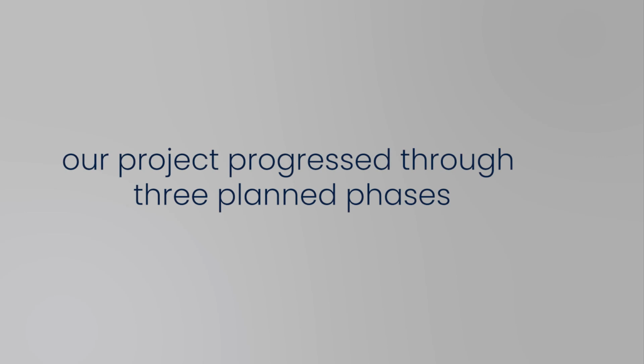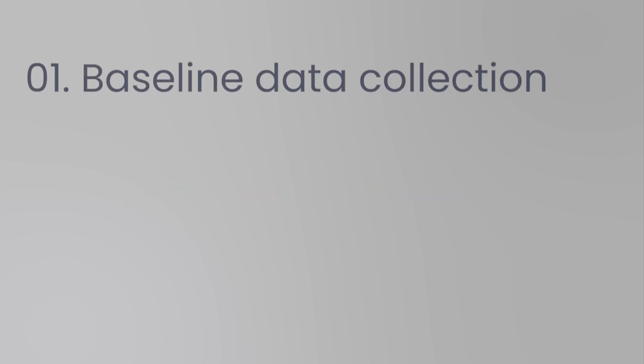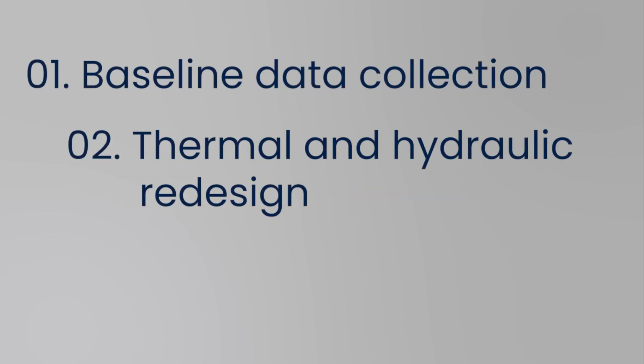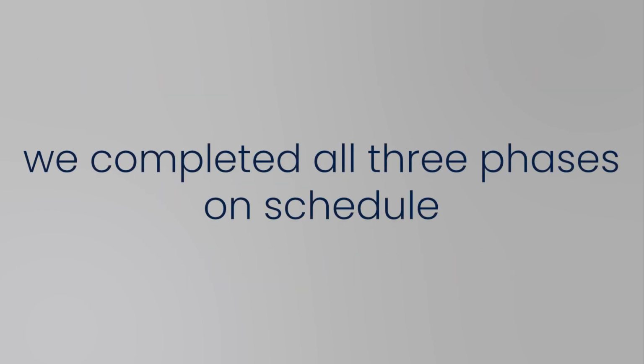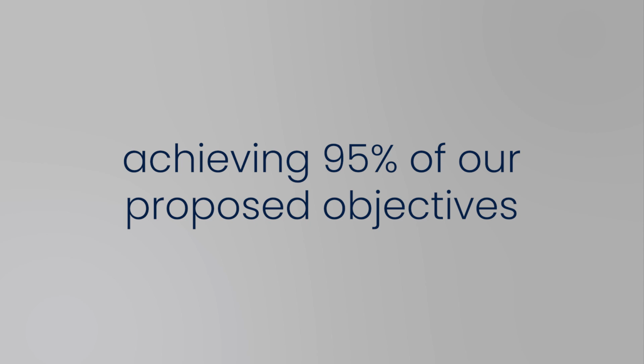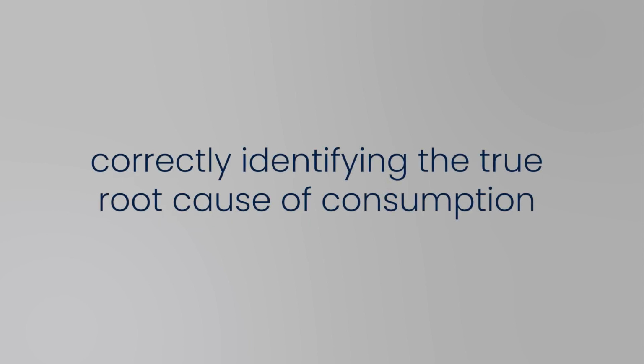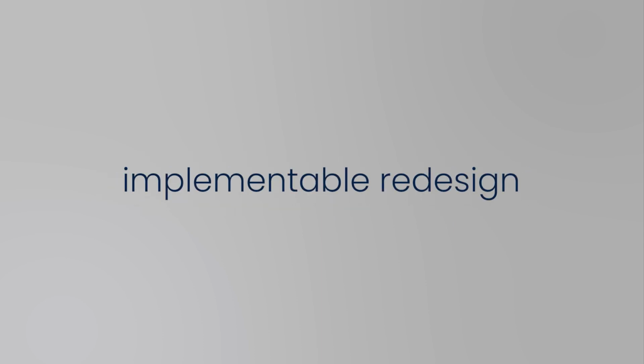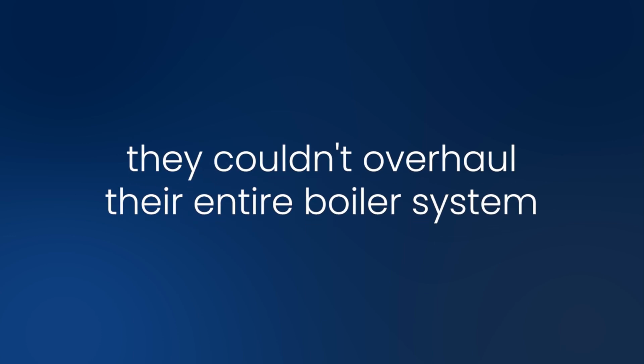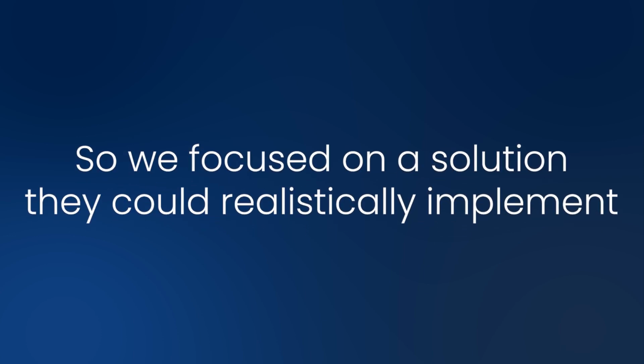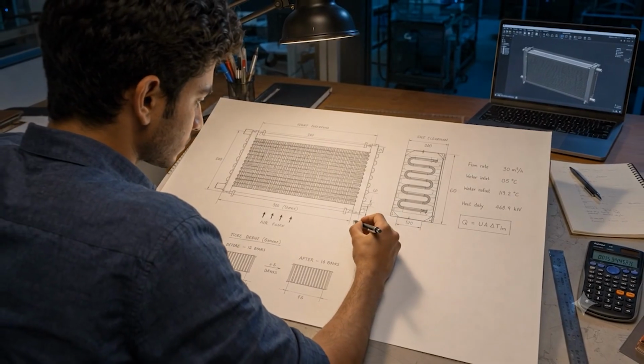Our project progressed through 3 planned phases: baseline data collection, thermal and hydraulic redesign, and system validation. We completed all 3 phases on schedule, achieving 95% of our proposed objectives, correctly identifying the true root cause of TRI's fuel consumption and delivering a validated, implementable redesign. TRI made clear that they couldn't overhaul their entire boiler system, so we focused on a solution they could realistically implement: redesigning the radiator itself.